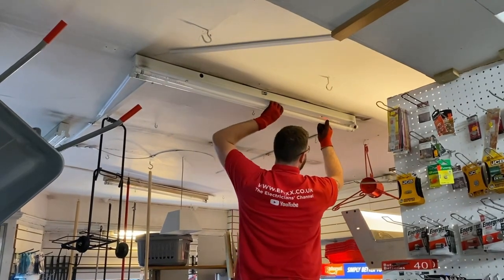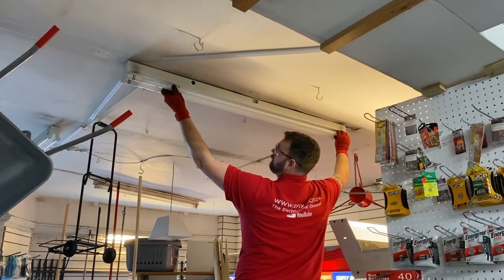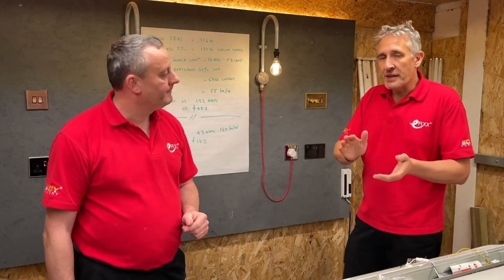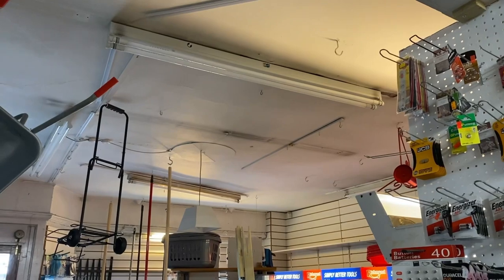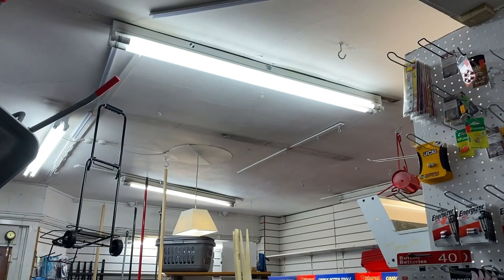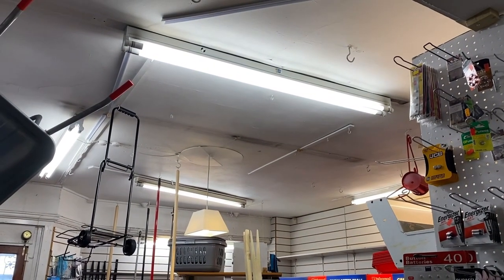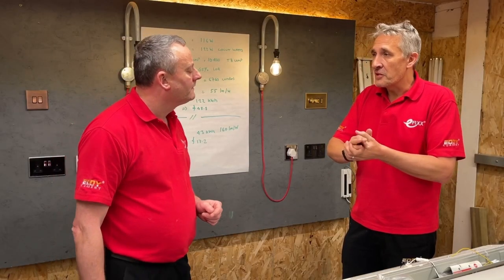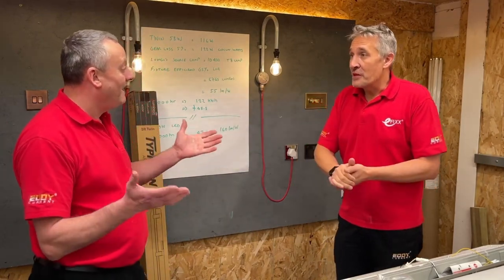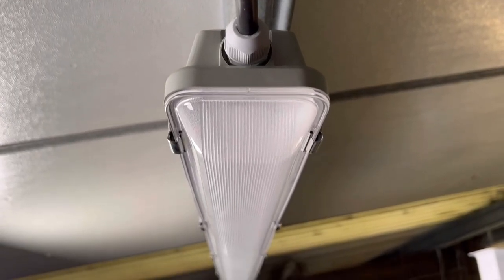Regular viewers are probably now shouting at the screen: what about just retrofitting it with an LED tube and leaving the existing fitting in there? LED tubes are great — you do get an energy efficiency gain, and there are good reasons to do that if it's a real challenge to replace the fixture, such as asbestos sealants. But you're still putting something more efficient in what could be an inefficient body, and you're still going to suffer from that 65% light output ratio. Really, if you can, the process should be to actually replace the fitting to get the maximum benefit.